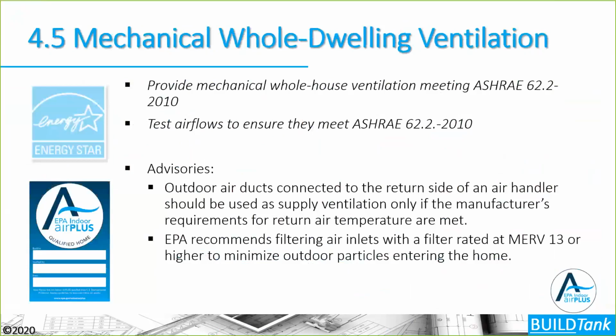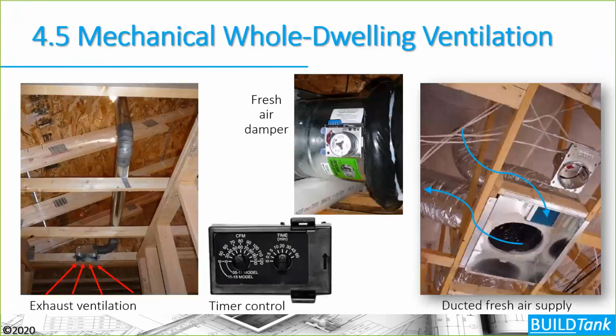Outdoor air ducts connected to the return side of the air handler should be used if you're doing supply side ventilation systems. You need to make sure that you're tempering that air, and that you're using an ECM motor if you're doing that, because that's another code requirement that's not specific to the Indoor airPLUS program. And then the EPA recommends a higher MERV system as well, a MERV 13 system, and we'll see why that is. There are basically these three types of whole house mechanical ventilation systems that we talked about last time: exhaust ventilation, supply ventilation, or balanced ventilation systems.